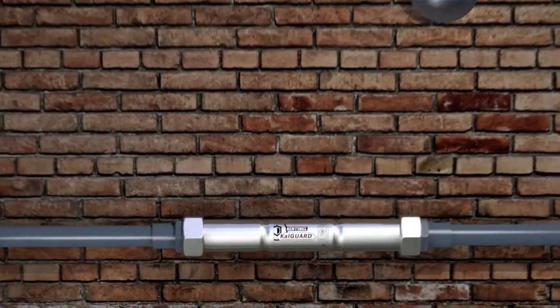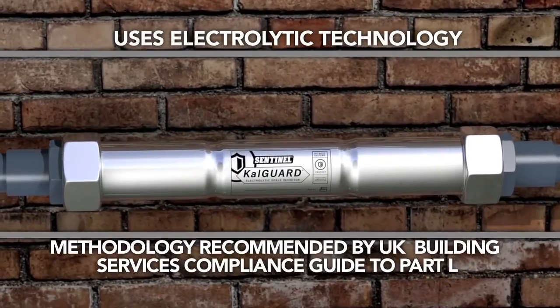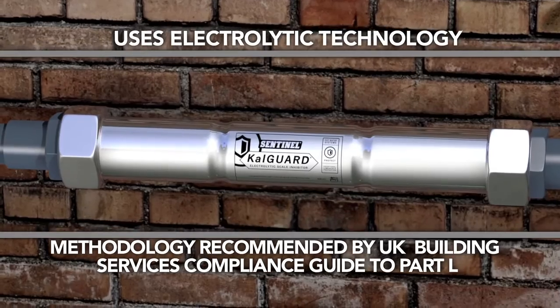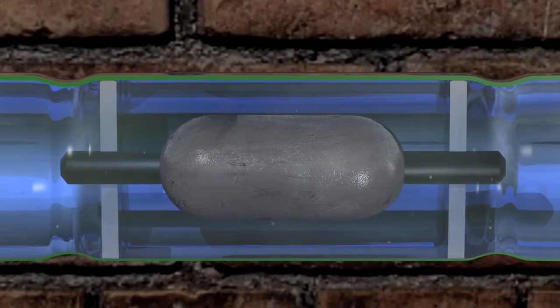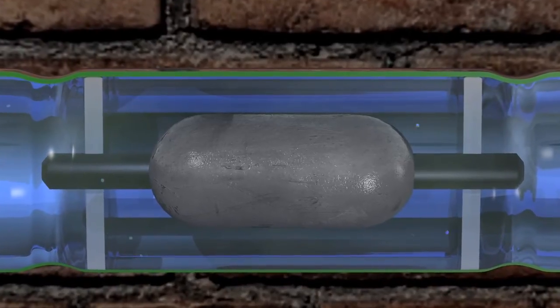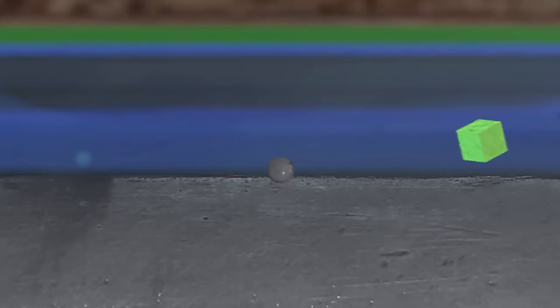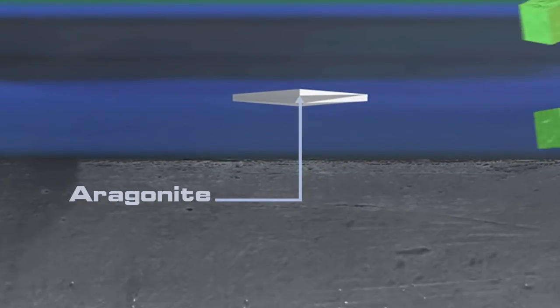Independently proven, KalGUARD uses electrolytic technology — a methodology that is recommended in the UK Building Services compliance guide to Part L. KalGUARD works by delivering very low levels of zinc into the water via an internal zinc anode and copper cathode arrangement.